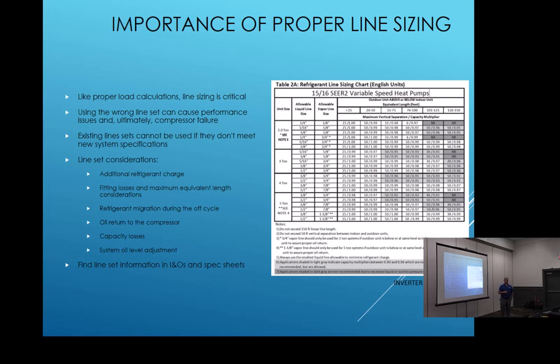But there's a caveat to that, because if you read the line set sizing instructions, it tells you you're supposed to use the smallest line set available. This really saves you from going to that house that has 1 1/8 already run in the wall for a normal change out. Before, you had to change it to 7/8. Now they're just saying you don't have to, basically. If you're installing a new line set, you need to follow the line set requirements and put 3/8 and 7/8 if that's what you need for that line set, to make it run properly, depending on how far away it is from your unit, basically is what they're saying.